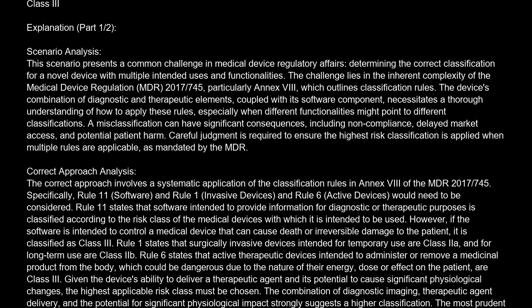Explanation. Scenario analysis. This scenario presents a common challenge in medical device regulatory affairs, determining the correct classification for a novel device with multiple intended uses and functionalities. The challenge lies in the inherent complexity of the Medical Device Regulation, MDR 2017/745, particularly Annex VIII, which outlines classification rules. The device's combination of diagnostic and therapeutic elements, coupled with its software component, necessitates a thorough understanding of how to apply these rules, especially when different functionalities might point to different classifications.